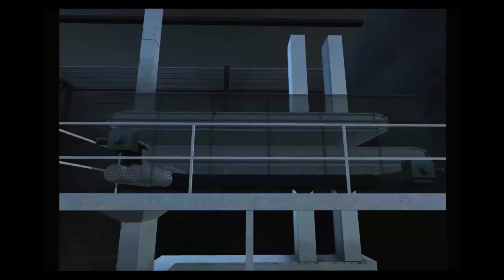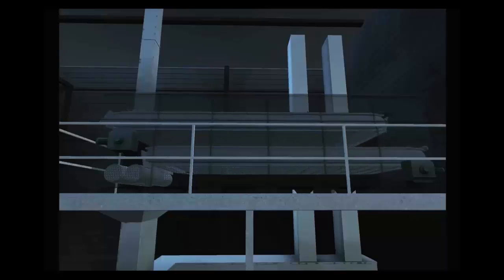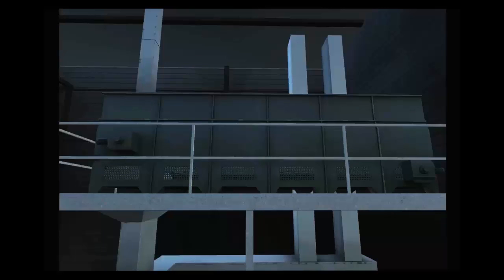It is important to keep the bed depth level in the cooler as the air will take the path of least resistance and only cool the pellets in the shallow part of the cooler bed.